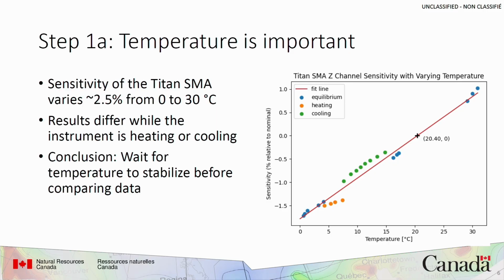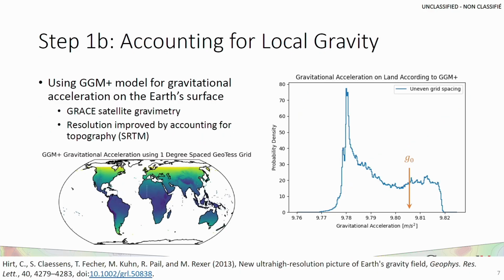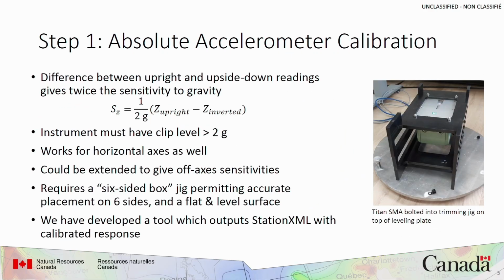Absolute accelerometer calibration works by taking readings right side up, whoops, and upside down and taking the difference. The main requirement is a 6-sided box jig, which facilitates accurate placement. It's shown in the picture on the right in an upside down position. The even trickier position is the one where the cables are pointing down and you have to stand it upright without interfering with those cables.